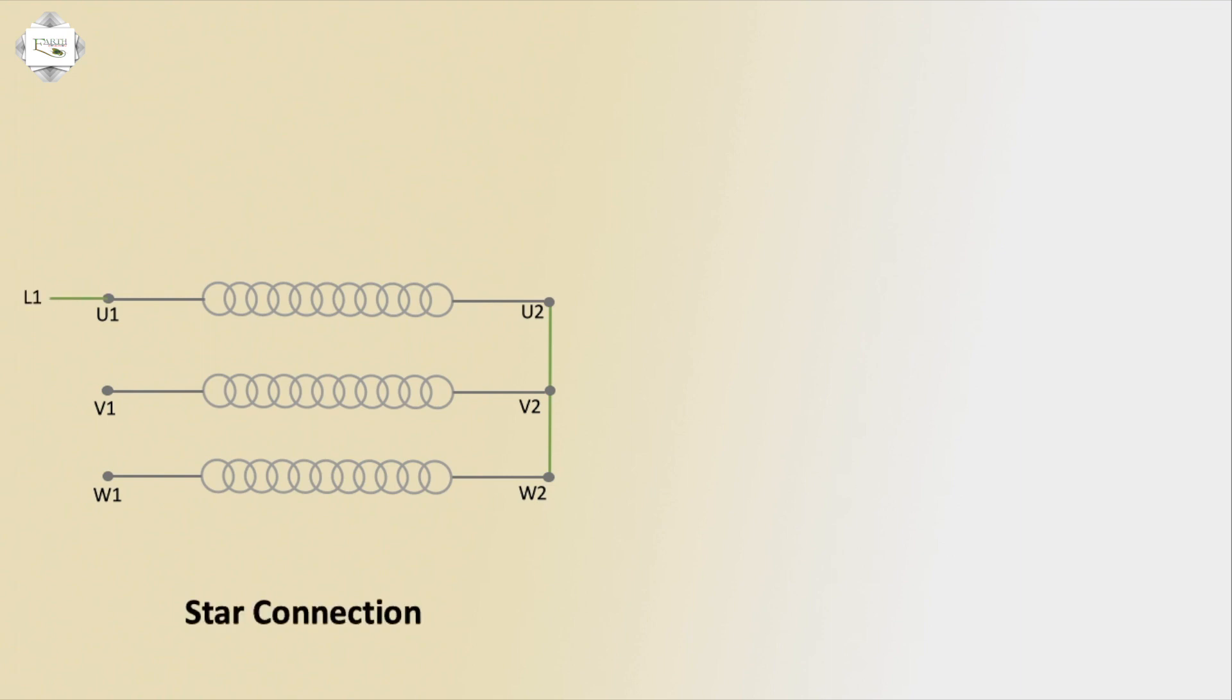Star connection: U1 connects to L1 first phase red, L2 second phase yellow connects to V1, L3 third phase blue connects to W1. This is the 3-phase star connection configuration for the motor.